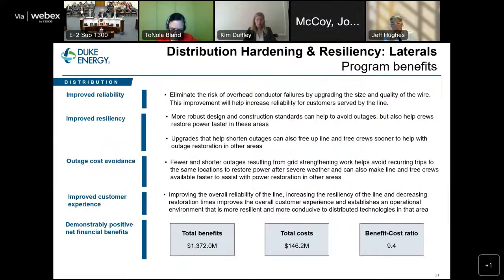So the benefits of hardening and resiliency for laterals: reliability and resiliency, eliminating the risk of outages increases reliability and improves resiliency. A modern high-strength conductor provides the ability to withstand limbs falling on it and other impacts that an older conductor with a corrosion risk may not support as easily. Upgrading historically outage-prone assets lessens the quantity and duration of outages, so overall system resiliency and reliability increases.